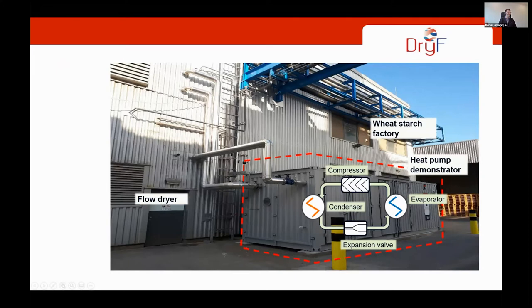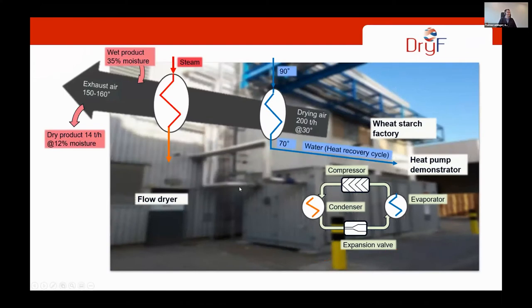And as I already said, outside of the wheat starch factory next to the flow dryer, we are integrated into our air drying system. The wheat starch factory is connected with the flow dryer by having a huge demand of air to be heated up, starting with our water exchanger, which is loaded by our heat recovery cycle. You can see here we have approximately a 90 to 70 degree drop. Then followed by the air exchanger, we have our exhaust air at about 150, 160 degrees Celsius, where our wet product containing 35% moisture, the wet starch, becomes dried to a dry product of approximately 12% moisture content.